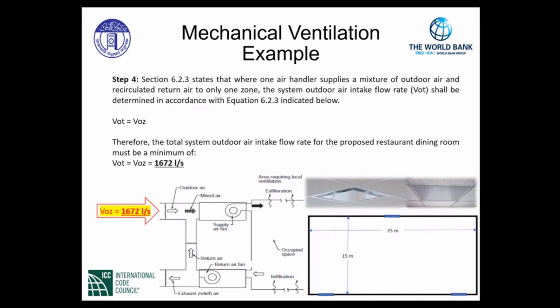1,672 liters per second. As indicated in the graph, it will be designed and balanced such that we will provide this amount of outdoor airflow rate into the air distribution system, mixing it with return air, in this case, through the supply air fan and distributing it into the breathing zone accordingly. This is a good graphic of an example of how the air is returned back to the system on the lower part of the graph. Through the return air fan, we have exhaust relief as well as return going back up and mixing with the outdoor air and then resupplying it to the occupied zone. In this case would be our dining room.